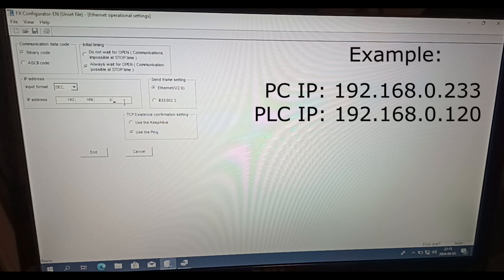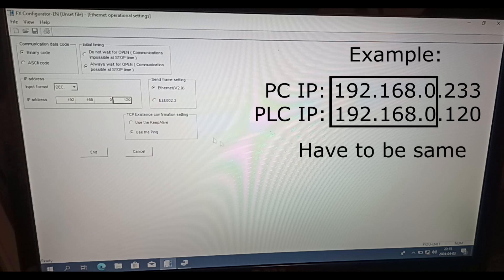Then we click on Operational Settings. Here we need to check the box that says Always Wait for Open. Then we can choose an IP address we want for our PLC. Remember that it has to be in the same subnet range as your computer to make a download.